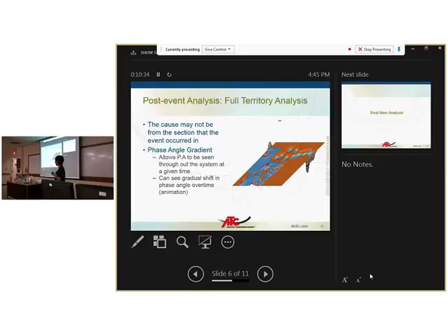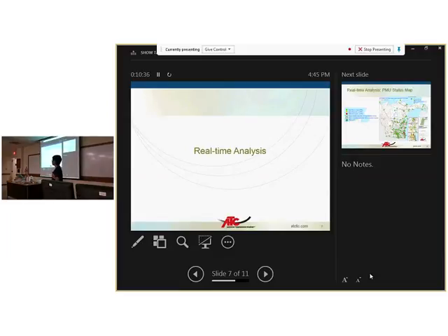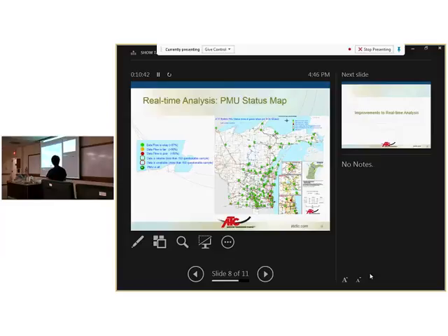Moving right along, there's the real-time analysis. This is a work in progress. One of the things I did up there is a PMU status map. As research about PMU data quality, synchrophasor data quality, shows, one of the biggest concerns about PMUs is that they lose time sync and stop putting out reliable data. Depending on the vendor, voltage might go from 138 kV to 0 all of a sudden, and that might alarm it.